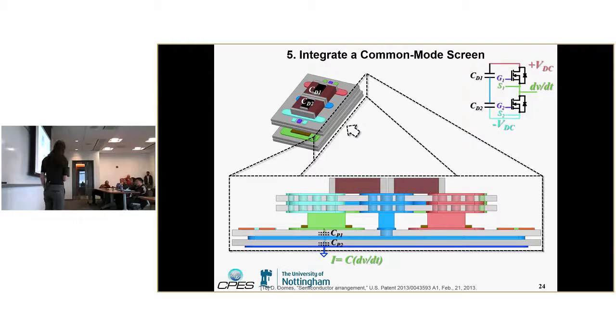Now you've got this parasitic capacitance at your output. This potential is always jumping, right? Based on which switch is on, this is either at your positive DC bus or your negative DC bus, so there's always a dV/dt transient happening here. When you have these parasitic capacitors in this ceramic material, that forms a path for common mode current to flow through the system ground.